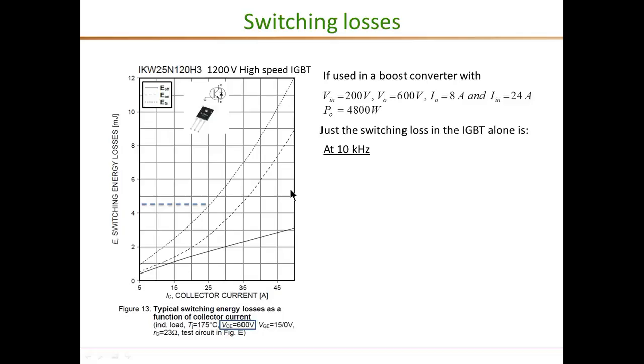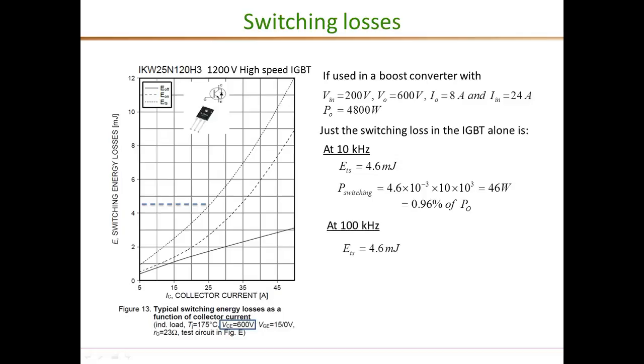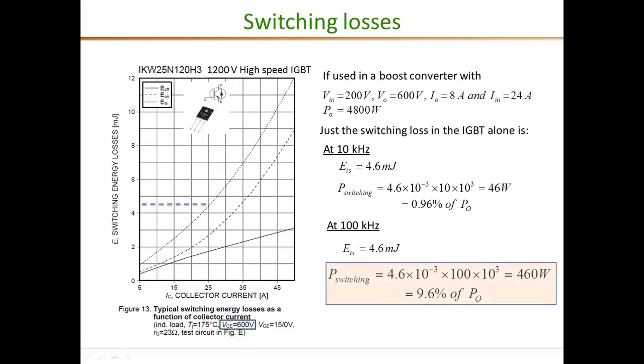Using this information, in our example with a switching frequency of just 10 kilohertz, the total switching losses can be calculated. At the given current of 24 amperes and 600 volt operation, the total energy loss comes out to be about 4.6 millijoules. That times the switching frequency of 10 kilohertz gives a total power loss of 46 watts, which is roughly 1% of the total power. If you increase the switching frequency to 100 kilohertz, the total energy per switching transition is still 4.6 millijoules, but the average power loss becomes 460 watts — almost 10% of total output power.